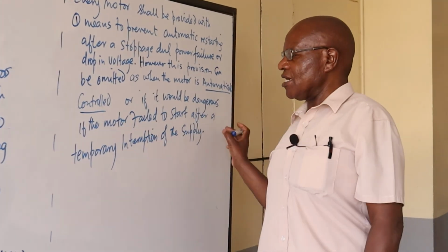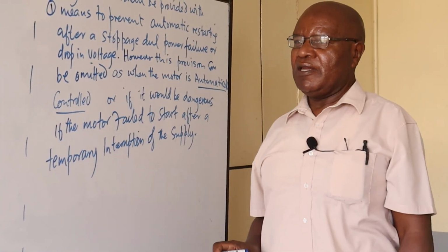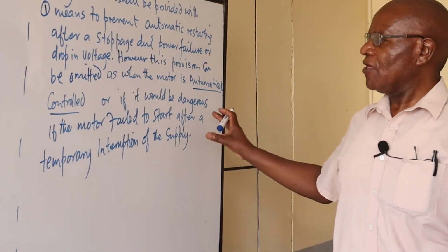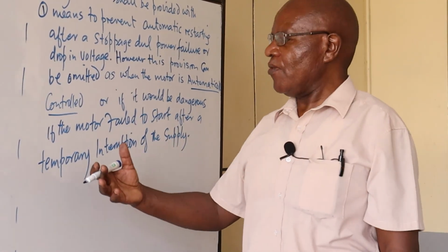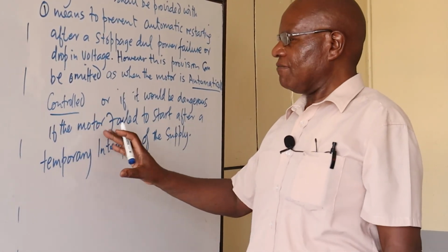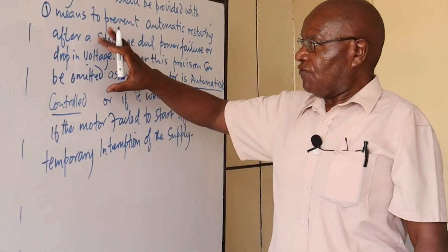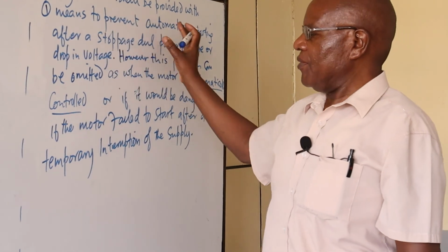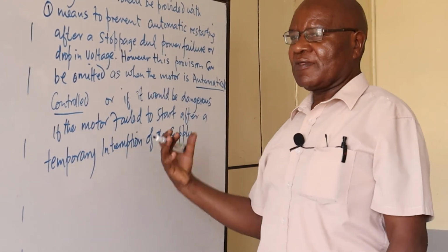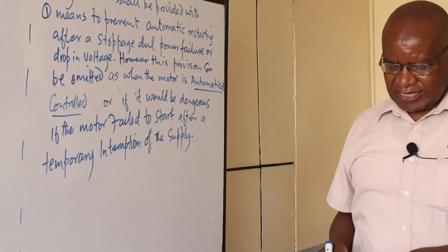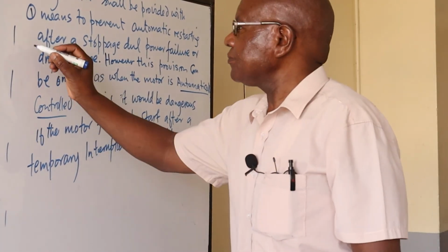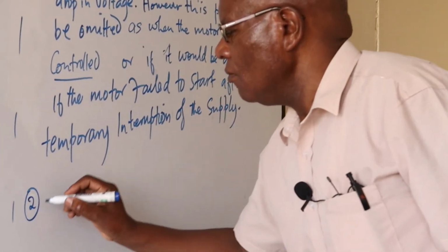If the motor failed to start, maybe in hospital theaters, whereby power supply is required, any motors connected there, maybe pumping the oxygen and the like, this bit of preventing restarting is done away with, so that when the power comes back, the system can be restarted again.